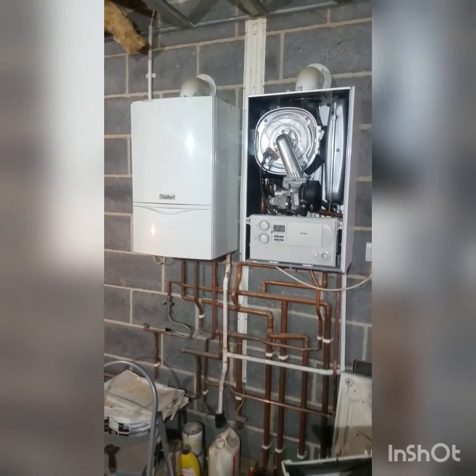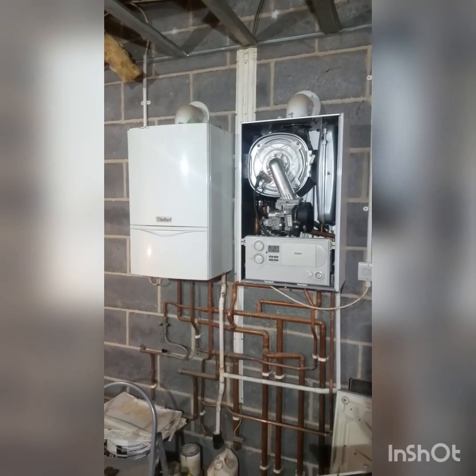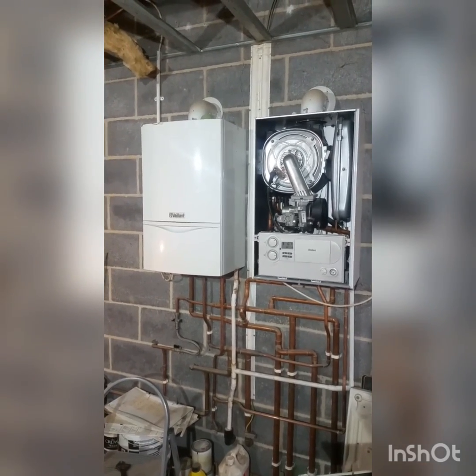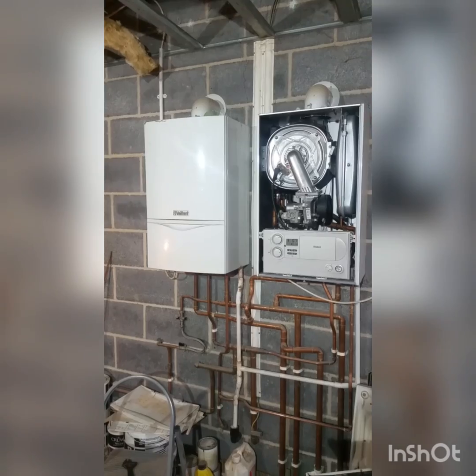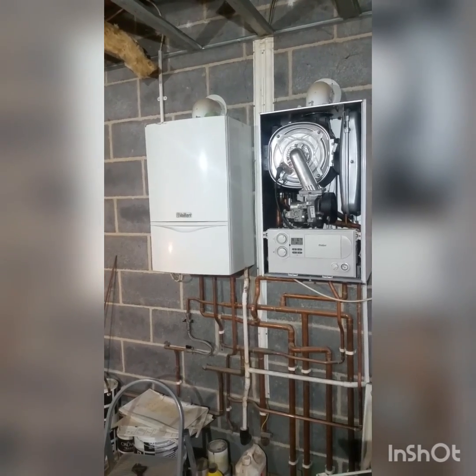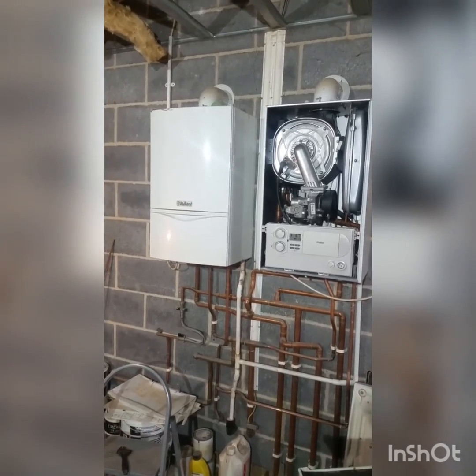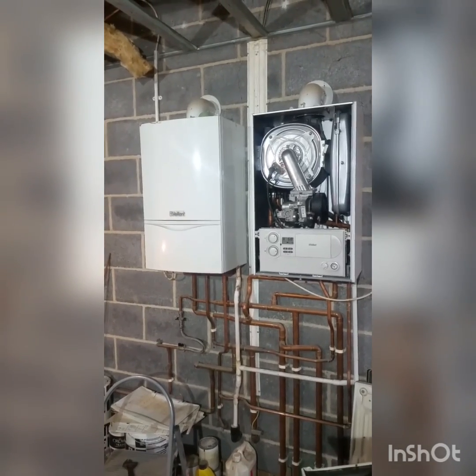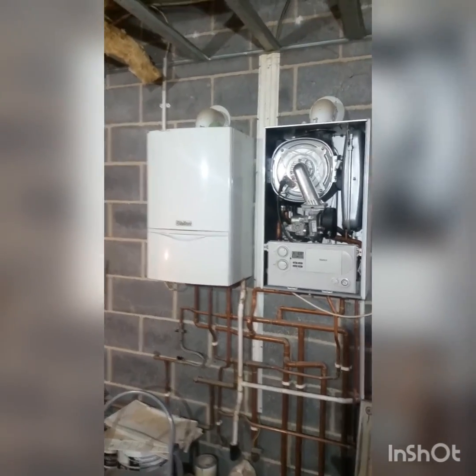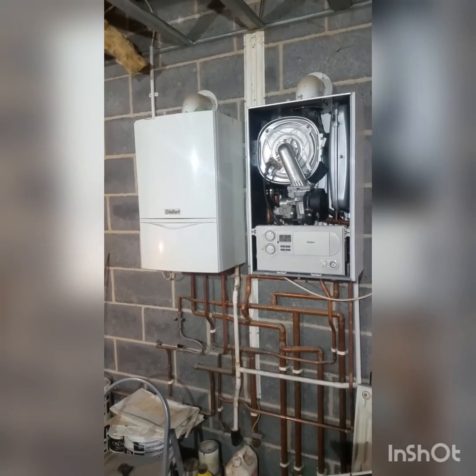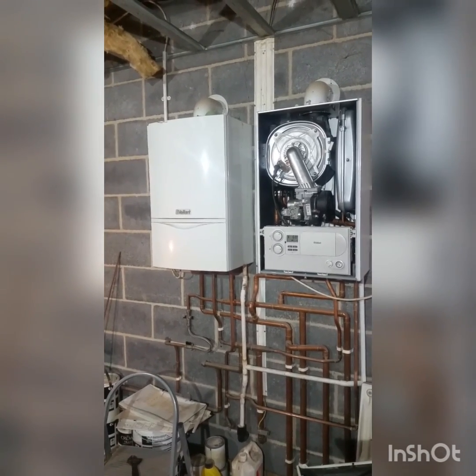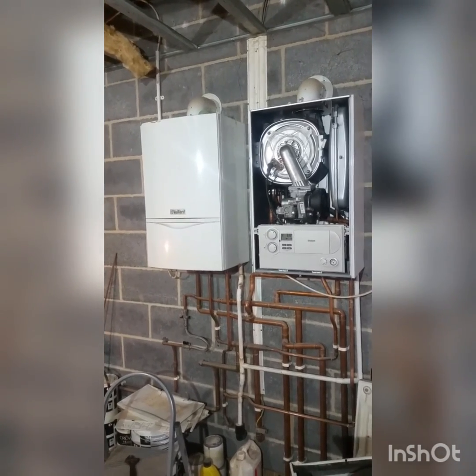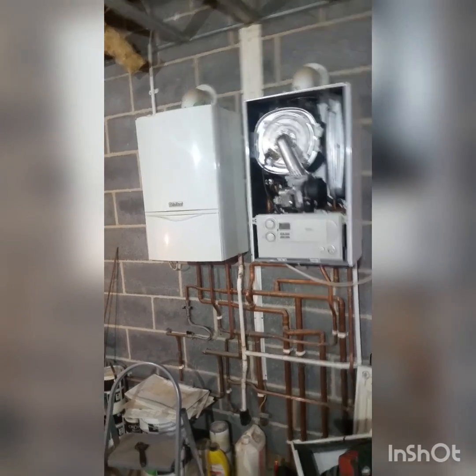So when I diagnosed the leak on the one on the right hand side, I isolated that boiler, left the system, and that's been left for about a week, and I've got a pressure drop in the time I was away on the remaining system with boiler attached. So I'm about to strip down the other boiler and just see if we've got a similar problem with a failed heat exchanger in that one as well, and if so I'll replace that heat exchanger also. But interesting job.